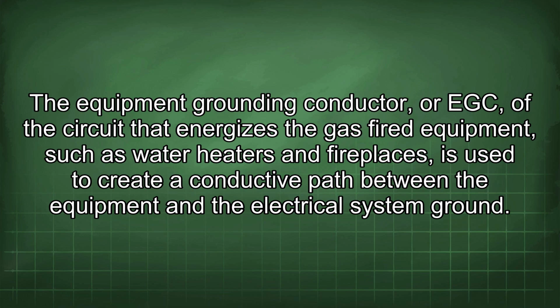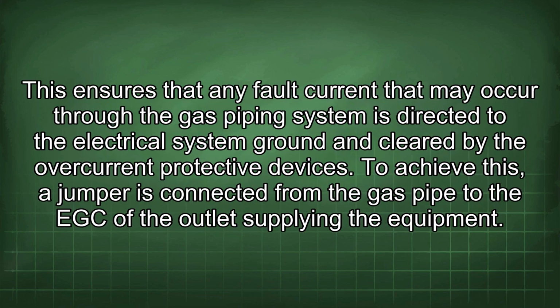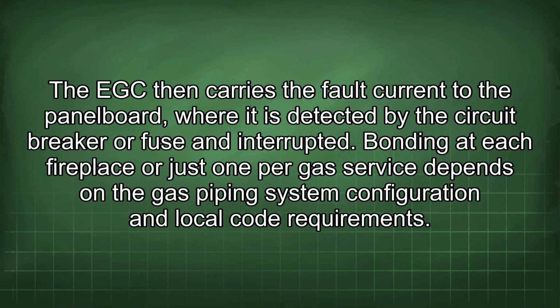The equipment grounding conductor, or EGC, of the circuit that energizes the gas-fired equipment, such as water heaters and fireplaces, is used to create a conductive path between the equipment and the electrical system ground. This ensures that any fault current that may occur through the gas piping system is directed to the electrical system ground and cleared by the overcurrent protective devices. To achieve this, a jumper is connected from the gas pipe to the EGC of the outlet supplying the equipment. The EGC then carries the fault current to the panel board, where it is detected by the circuit breaker or fuse and interrupted.